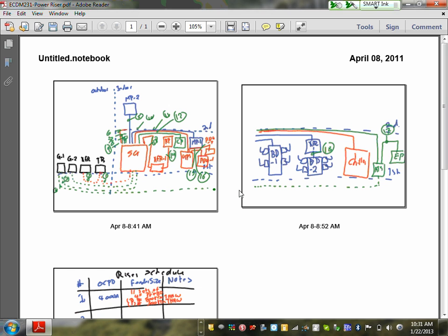That's not necessarily what's going on in your project, but I'm just trying to explain all the different things that we do. At that point, instead of just dropping the utility and going to gens, that's a big jolt on these generators. They do something called a soft load transfer where they slowly bring these generators up to speed, slowly picking up the load. Once the generators are up to speed and able to take it, they'll shut off the utility so the generator doesn't see that big pop, that punch.